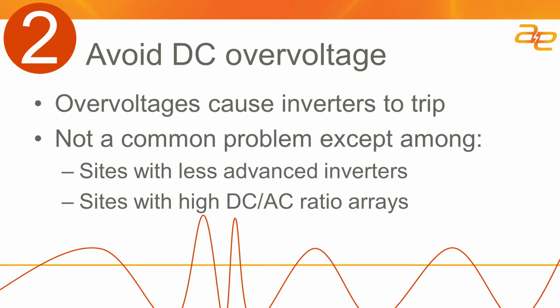Early in my career, I saw a lot of sites where we had to put in some electrical, mechanical switching so that when the DC voltage was getting too high and the inverter was at risk of tripping, we would drop out some of the DC in order to manage that DC voltage and keep it in spec for the inverter to take. With today's inverters, they're a little more tolerant of wide DC voltage ranges, but there still is an upper limit to what an inverter will accept and operate in MPPT. So if you've got a very high DC-AC ratio, you're more likely to run into trouble here.